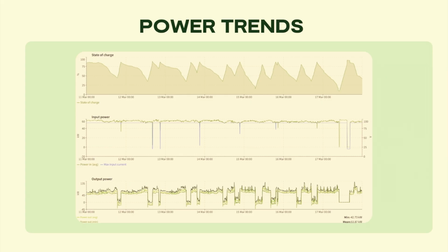How does that look in our data projects? You can see the state of charge going down here. That's basically because the load is too high. So you can see the input power over here. We're getting almost 60 kilowatts from the grid, but you still see that the state of charge is dropping down. So that means the grid doesn't have enough capacity to supply the full load. So you see at this point, we turn on a generator. And the generator, in this case, is on fixed power output. So it just pushes a fixed amount of power back into the battery.